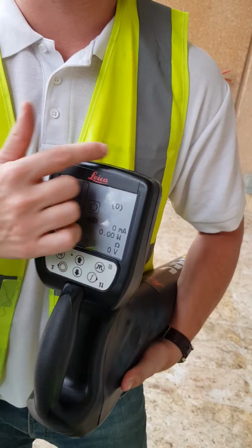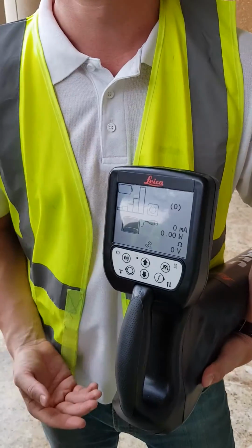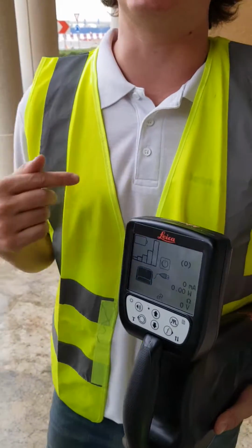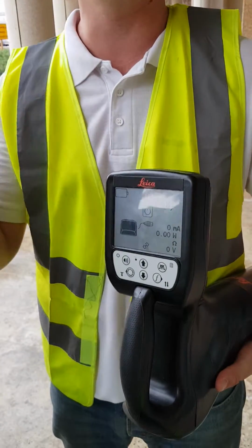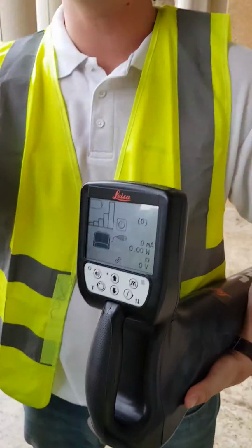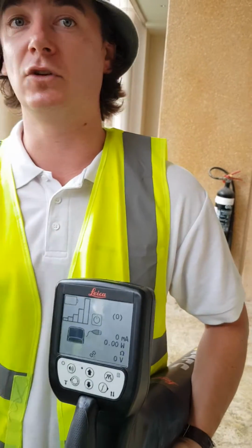It's a good indicator. You can quickly flick on here just to see if you've still got transmitter signal running through. Because yesterday we had to walk back to the transmitter, I realised the tone was beeping and it wasn't a solid tone, therefore we know the earth wasn't good, and we had to check both terminals, so the red and the black, to make sure they had good connections.